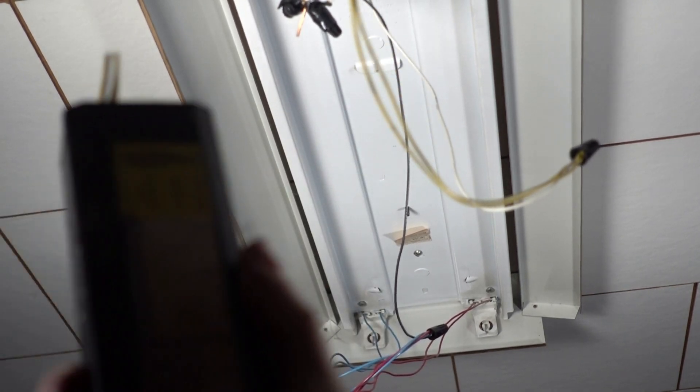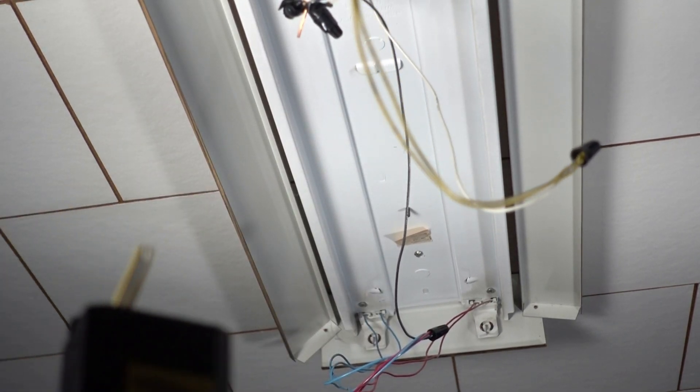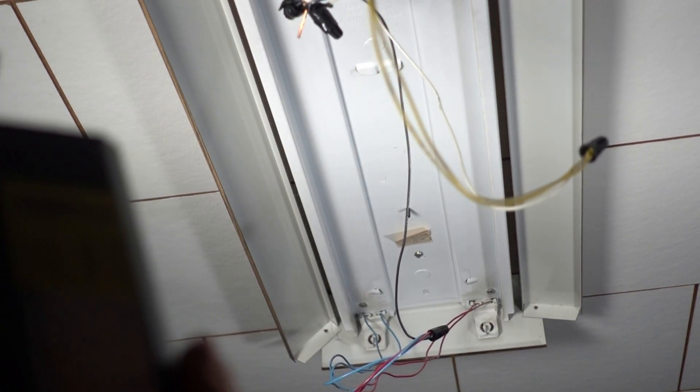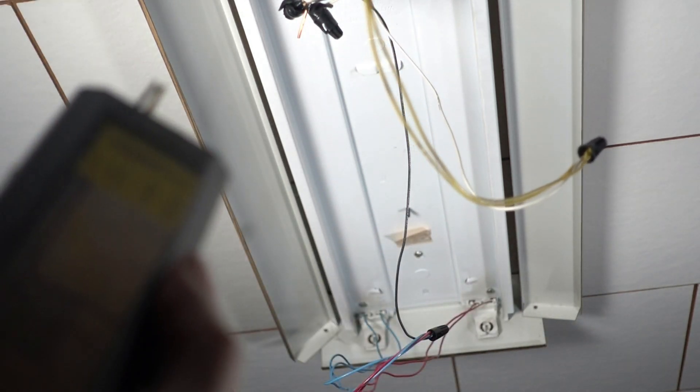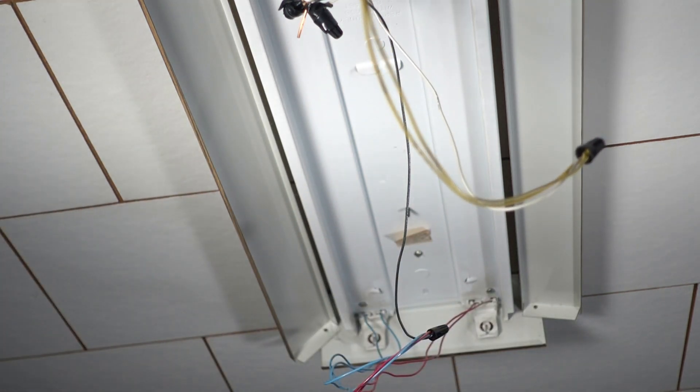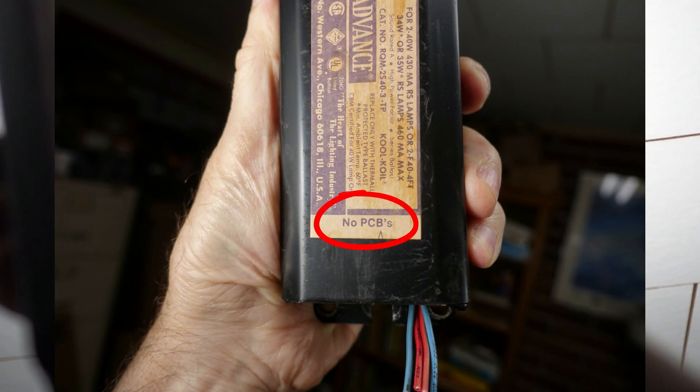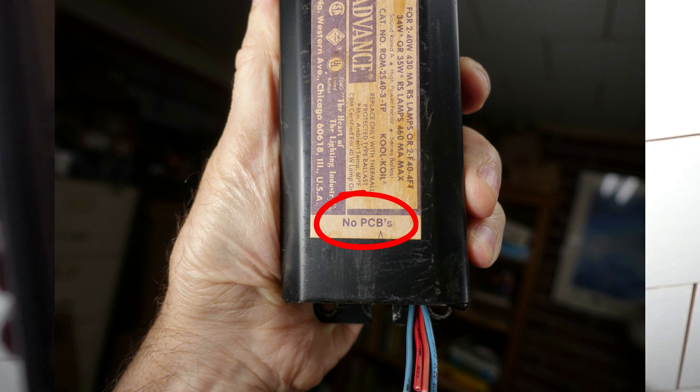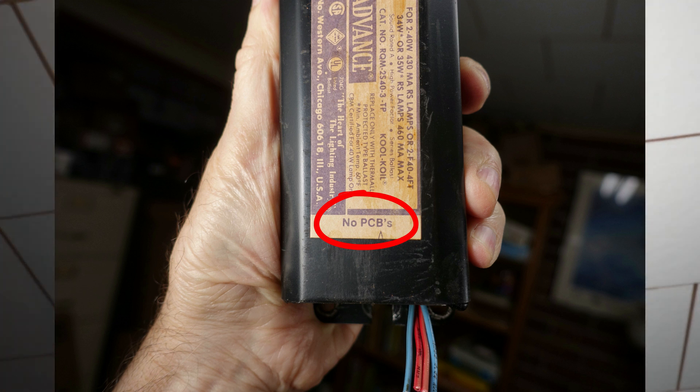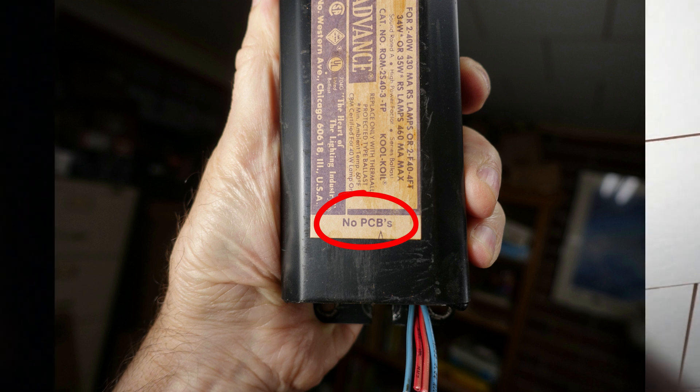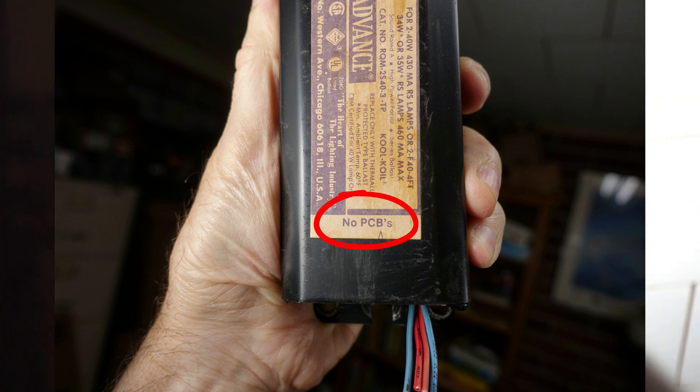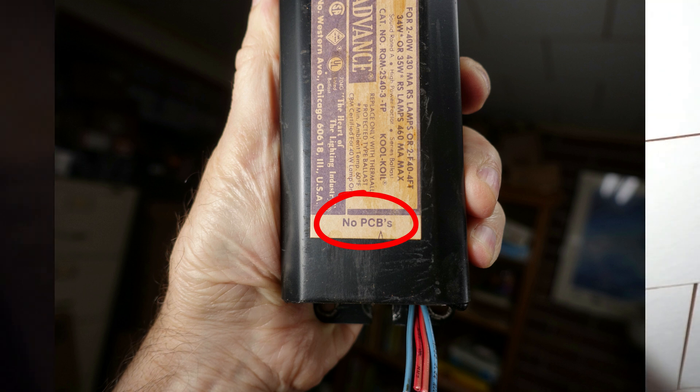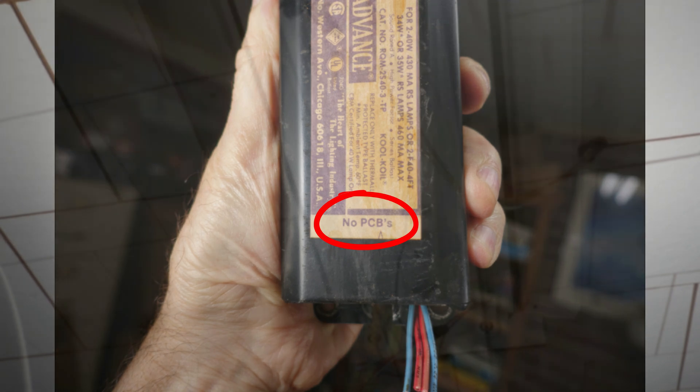On these ballasts, if it says there's PCBs, if it's got that dangerous chemical in there, you've got to take it to a hazardous dump site. This one, it's PCBs, and this one, there's an actual label on there that says no PCBs. Since it has no PCBs, that could go in your metal recycle container for curbside pickup.